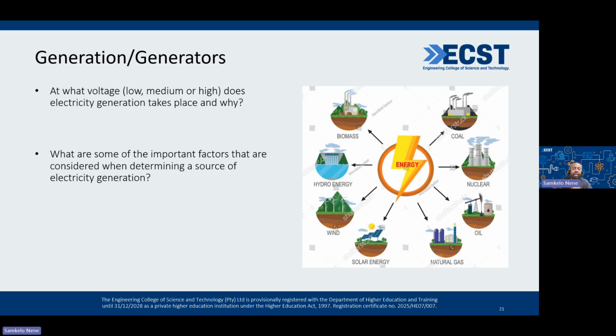The reason generation is at medium voltage is because we are trying to maximize efficiency and also meet insulation requirements. For example, transmission is done at a higher voltage because we are trying to avoid losses. If you look at the towers you see outside while driving, with wires, that's our transmission network, and between the wires there is air which provides insulation.